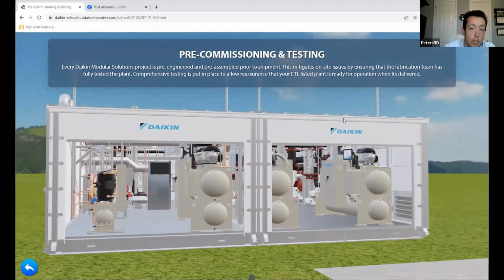So this is a complete solution. The plant is ETL listed, and we have testing logs—all pipes and fittings are tested before it comes in. We have a lab in Phoenix where we can run the chillers, cooling towers, boilers, everything. We can simulate a load and run through all your sequences before this ships out. Big advantage if you have critical operations that need to come online right away.